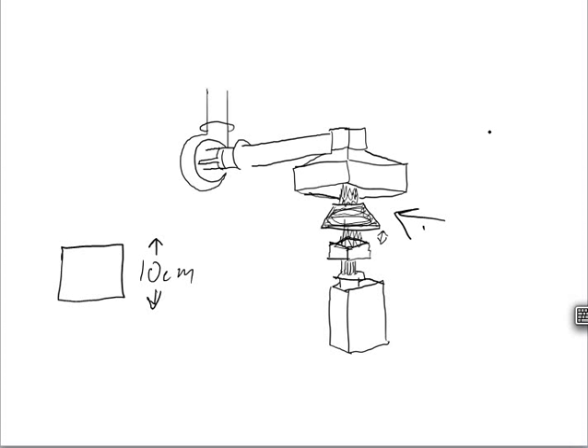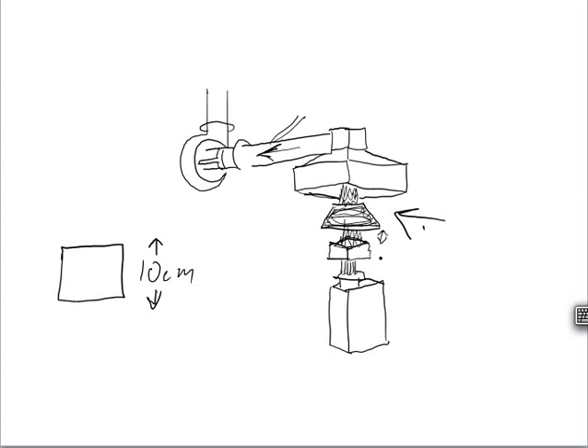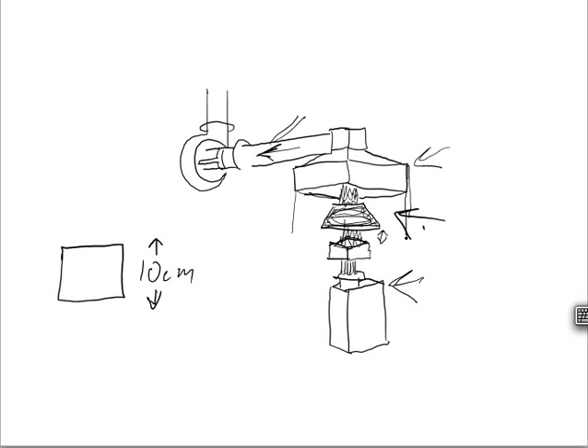It does test samples with excess air, and measures heat release rate using the oxygen consumption method. So you're looking at how much oxygen is gone in your flue duct. As it comes up through here, you pull a sample gas out. And then we also have our sample on a load cell. We have a load cell here. This is our fume hood. There's sometimes a cover that goes on to help keep gas from any excess combustion products from escaping. We have a pump here that drives our, that pulls our sample gas out.